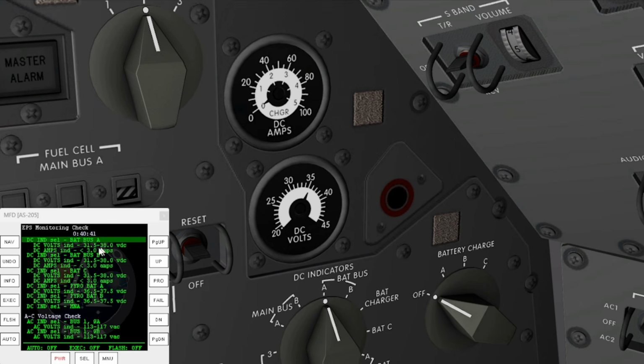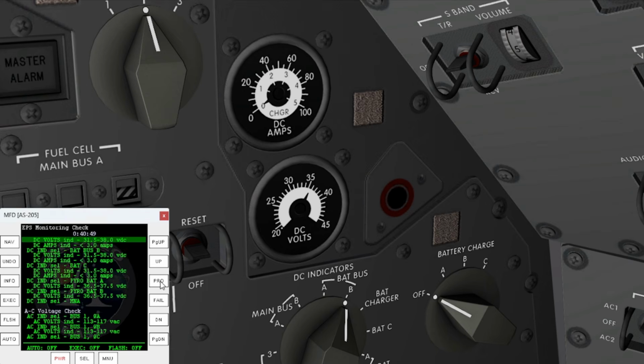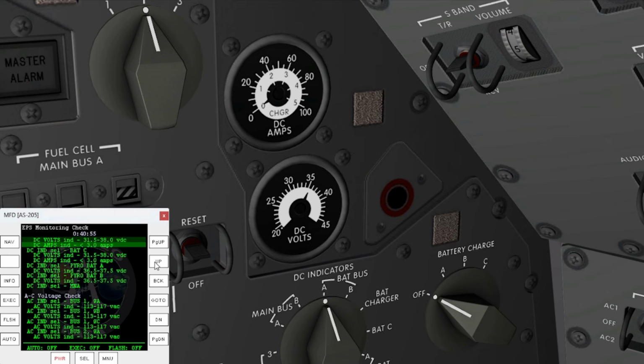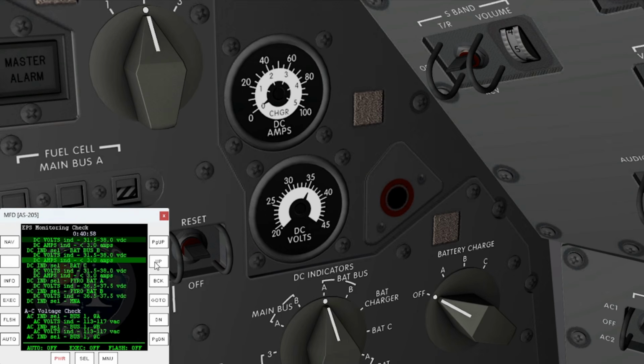BAT bus A, 31.5 to 38 volts DC. BAT bus B should be around the same, 31.5 to 38 volts DC. Less than 3 amps on both of those.